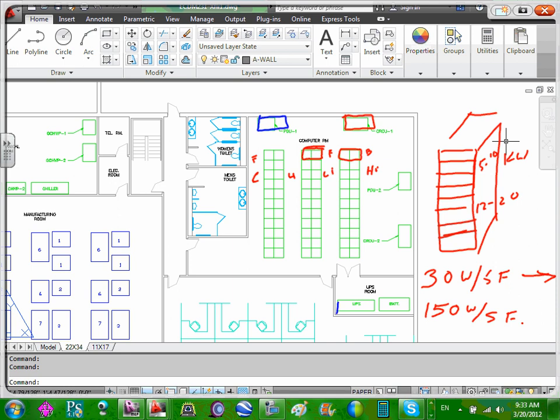So we're going to have, here's where I'm going to get in trouble. And as designers, you may have to come back and tell me that I'm going to lose some office space because my UPSs might have gotten bigger. So when you look at the UPS requirements and look at their sizing requirements and their layout requirements, if I need to lose a couple office cubes, I'm okay with that. My data center is becoming more important. So if you need to make that change, show me that we need to make this room bigger to get bigger UPSs in. So I'm not telling you what those sizes are, but I'm guessing when I make them big enough to handle 150 watts a square foot. And I'm going to talk about the entire raised floor area, which will include some battery.